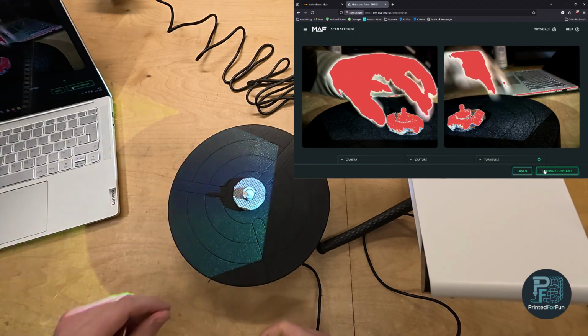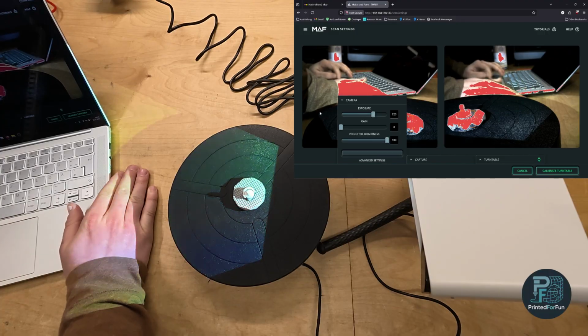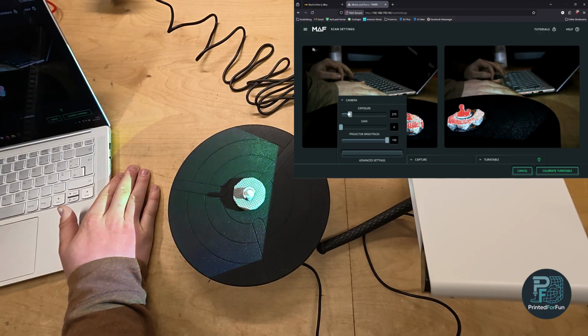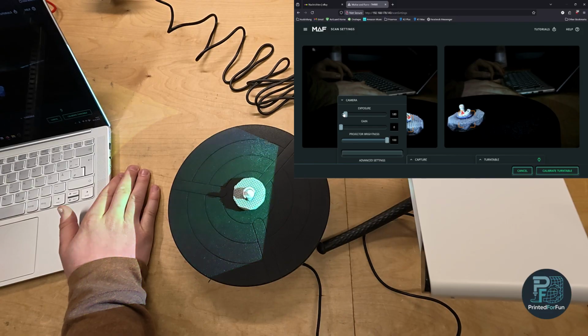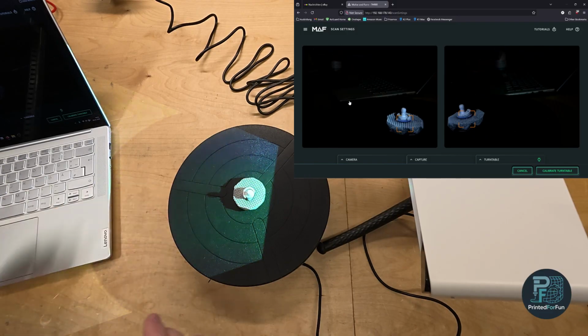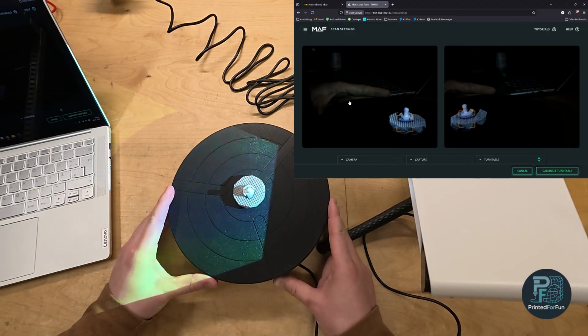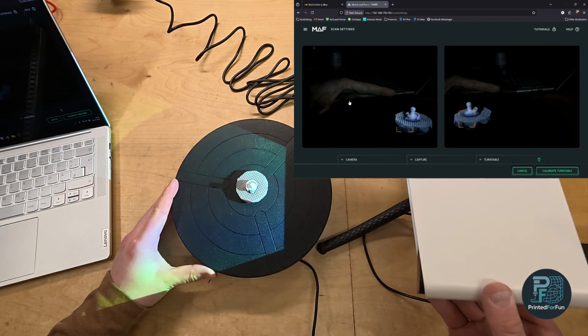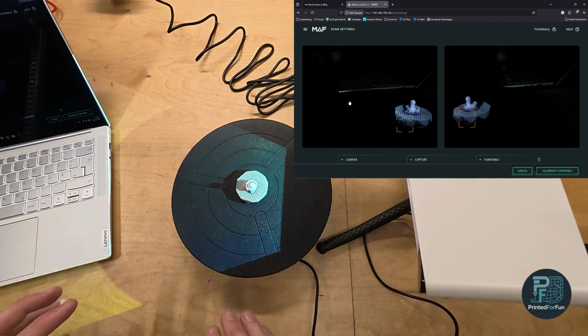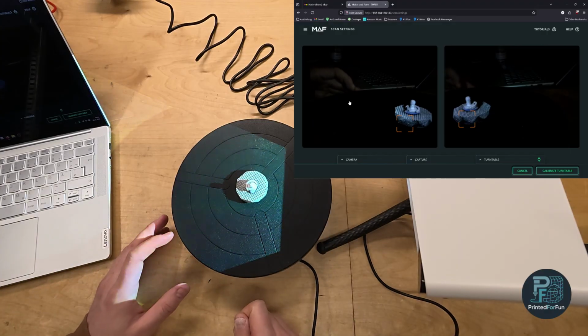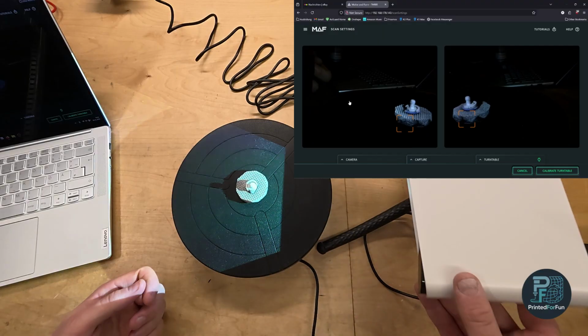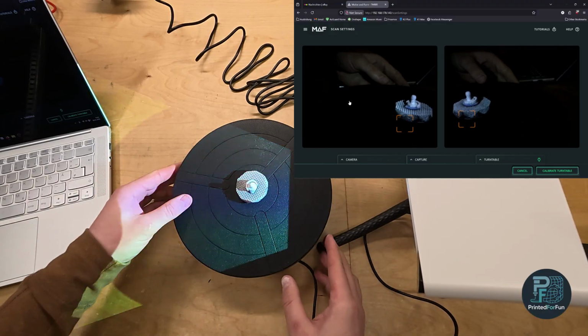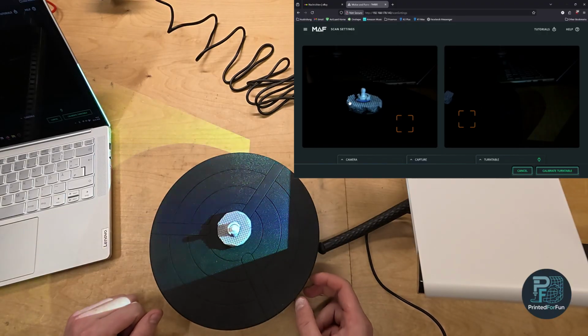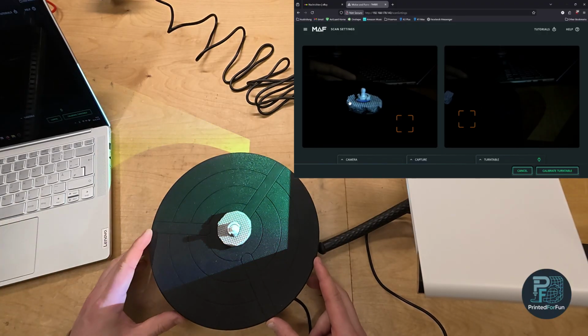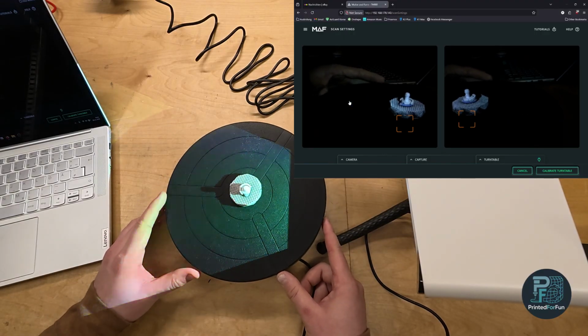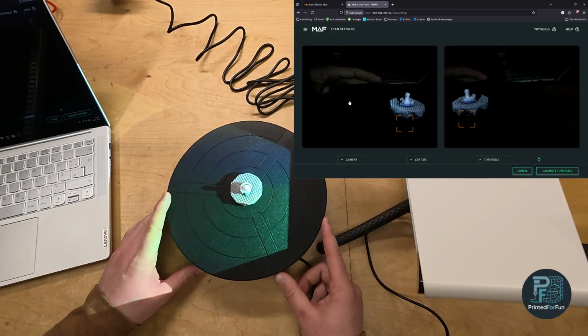That's quite nice. So now you can see with the scan spray we are quite overexposed. So let's drop down the exposure quite a bit, so we don't have any red spots. And now we can also talk about the placement of the part. Ideally, both cameras see the same image or roughly the same parts of the model you want to scan. Of course, for the scanning to work, both cameras need to see the model. So what wouldn't work is if I place the scanning table like this and only one camera sees it, or on one camera it's centered.